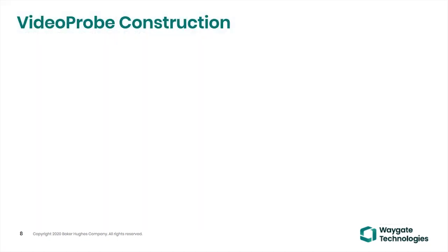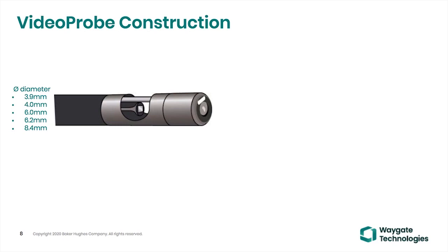So you've made an investment in a video borescope, and it's a significant investment. And what I'd like to talk about is how to protect that investment by cleaning it and protecting it. So in the world of video probe construction, I think it helps to understand what's behind the curtain, whether it's a small diameter 3.9 millimeter scope or a larger diameter 8.4.